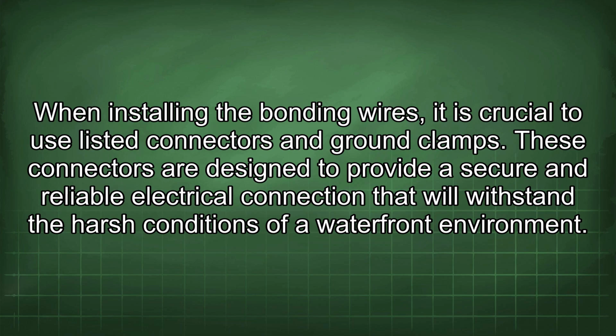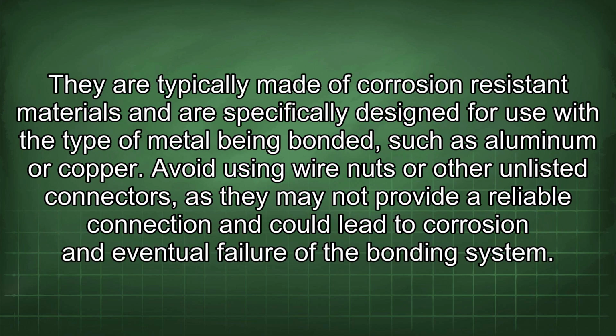These connectors are designed to provide a secure and reliable electrical connection that will withstand the harsh conditions of a waterfront environment. They are typically made of corrosion-resistant materials and are specifically designed for use with the type of metal being bonded, such as aluminum or copper. Avoid using wire nuts or other unlisted connectors, as they may not provide a reliable connection and could lead to corrosion and eventual failure of the bonding system.